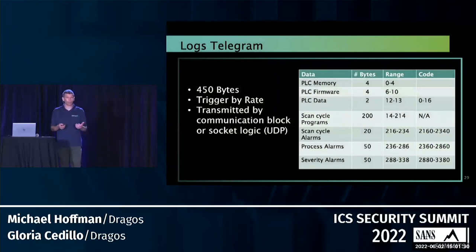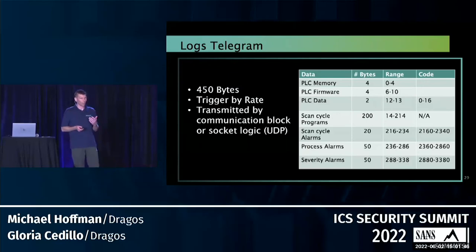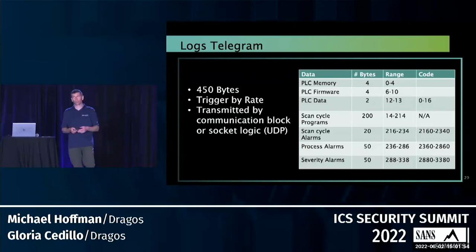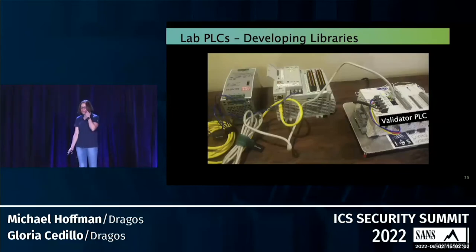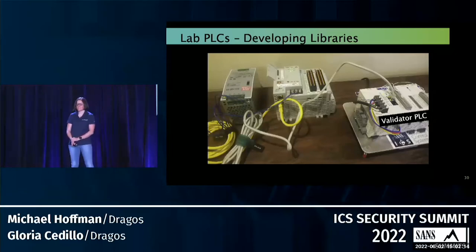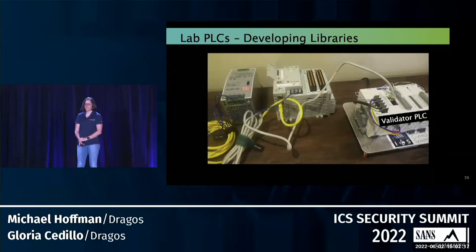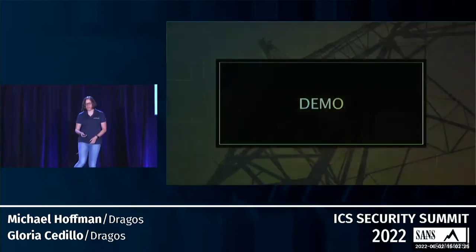This is an example of log forwarding — we're leveraging 450 bytes, which is the range Rockwell uses for log transmission. We're using the built-in capabilities of those functions, building in almost a protocol — a log format using the memory, firmware, and different data elements — and this can all be transmitted with UDP. For the demo, this is what we use to create the libraries: a Rockwell CompactLogix PLC, and then a validator PLC from the SANS ICS 612. The validator PLC checks the monitoring and also checks the firmware of the other PLC.